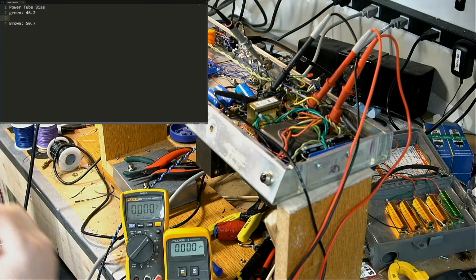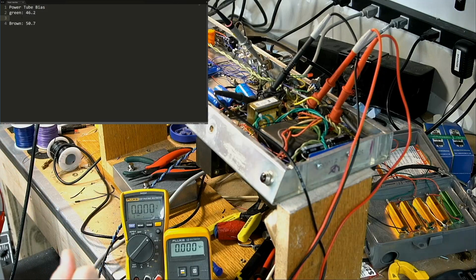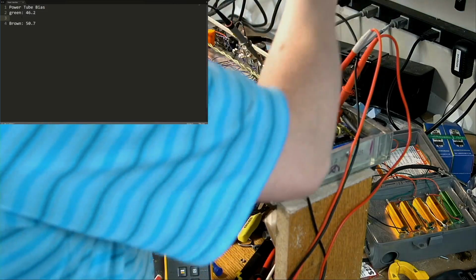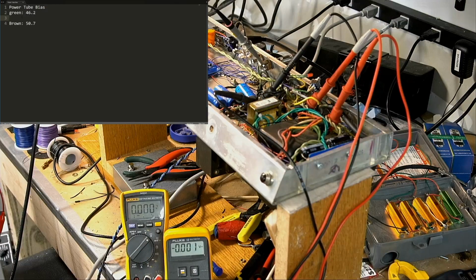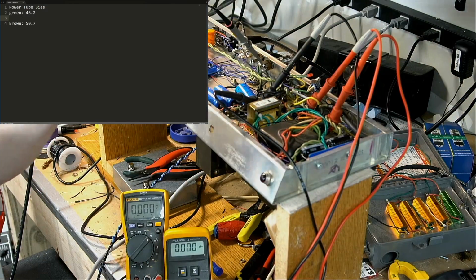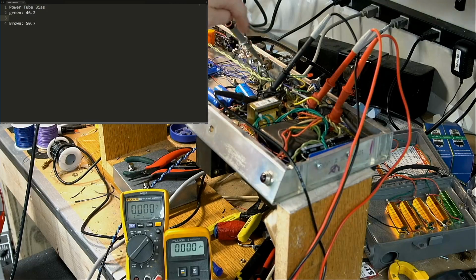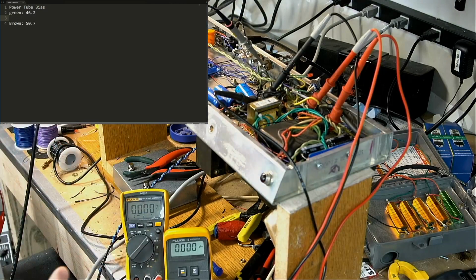I also need to know what the maximum voltage is, so I'll temporarily take one of these out and touch it to a grounding point to get the actual full voltage coming across. I've tested the voltage, and we'll double check those a bit later, but you also want to check the voltage across all the pins of each to make sure they're fairly consistent, and they were.